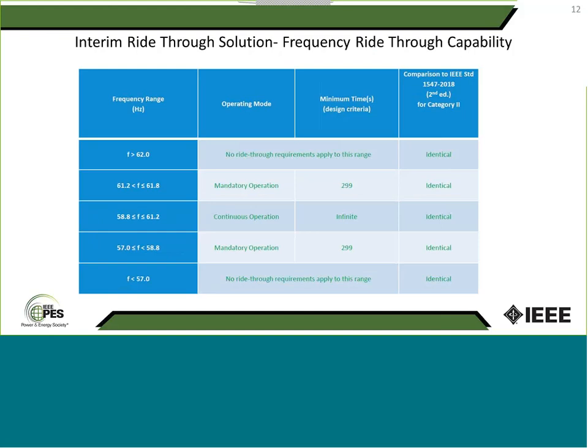you see for frequency, this table is from the 1547 standard. We have a continuous operation range, mandatory operation, and no ride-through range. And again, it was pretty straightforward. We really did not have any issues with frequency ride-through because of currently adopting the NPCC Directory 12 under frequency load shed curve. And we really don't use frequency relaying for protection anyway. So our protection folks were okay with this, they really did not care much when it comes to detecting faults and so on.